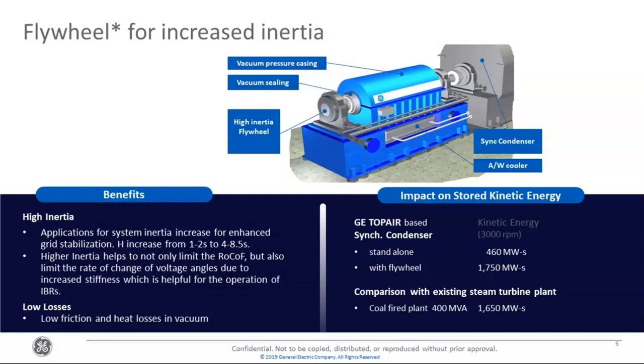And that is something that helps not only limit the rate of change of frequency, it also helps limit the rate of change of the voltage angles, because your system is generally stiffer because of the increased inertia and increased short circuit strength, and that is helpful for the operation of IBRs. As we discussed earlier, they need to be able to latch on to the grid angle properly, to the voltage angle properly.